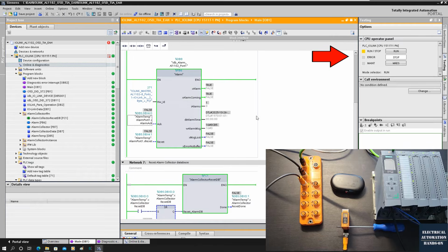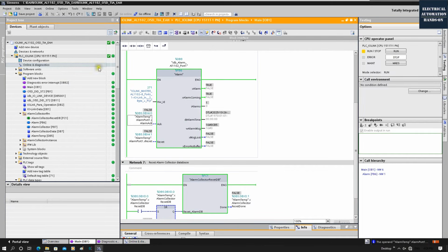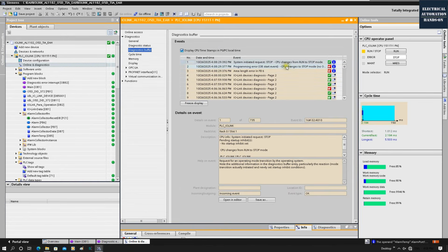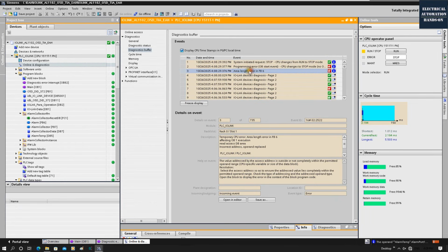Okay, so this is the case I found from this sample program. As we can see, almost the last alarm, I'm doing the alarm acknowledge. We will see, unfortunately, the CPU stopped. So let's troubleshoot what happened from this alarm diagnostic. If I jump in and go to this alarm, the CPU was stopped. Let's go to the reason here.